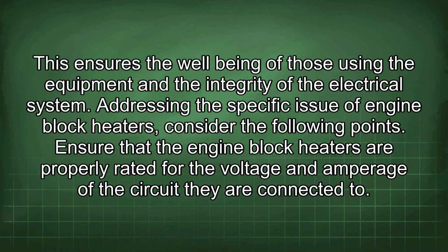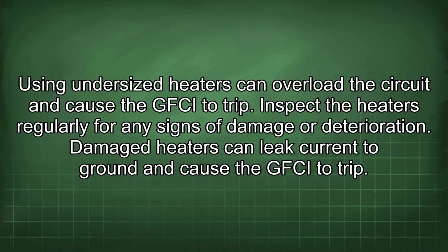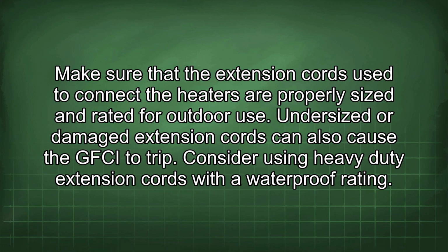Addressing the specific issue of engine block heaters, consider the following points. Ensure that the engine block heaters are properly rated for the voltage and amperage of the circuit they are connected to. Using undersized heaters can overload the circuit and cause the GFCI to trip. Inspect the heaters regularly for any signs of damage or deterioration. Damaged heaters can leak current to ground and cause the GFCI to trip. Make sure that the extension cords used to connect the heaters are properly sized and rated for outdoor use. Undersized or damaged extension cords can also cause the GFCI to trip.